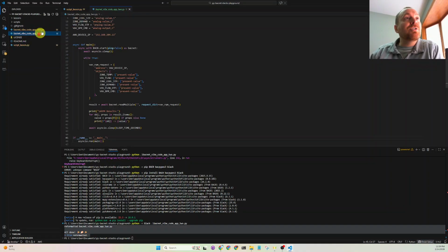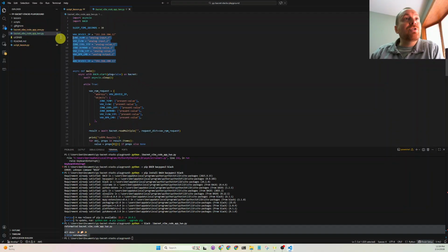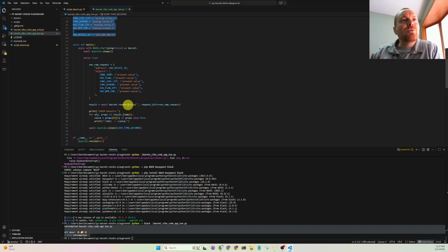My own personal opinion is you should just be hard coding this stuff, because it really limits the amount of requests on the network. AI was generating code to generate all of that data from a network request, but we can do that ahead of time with our BACnet scan tool. And then there's only one request. There's no whois, like we said earlier. Only do the whois if you're setting up a system, and never run it long term, continuously doing whois requests.